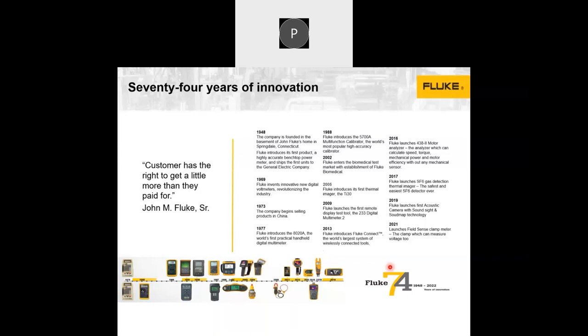Then in 2019, we launched our acoustic imagers, for leak and partial discharge detection. This is now revolutionizing the way people detect leaks, even for railway applications where pneumatic controls are used for stopping or pneumatic brakes. If these pneumatic lines are leaking, efficiency will be very low, or it may not work at times, and it is very difficult to find the leaks using soap water or traditional methods. That is where we are changing the way people see leaks, using an acoustic imager.